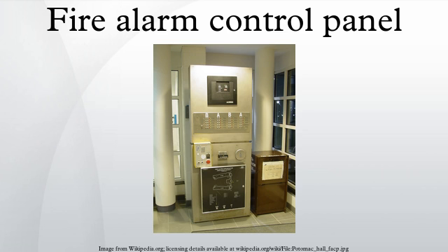A coded panel is similar in many ways to a modern conventional panel, except each zone was connected to its own code wheel, which, depending on the way the panel was set up, would either do sets of 4 rounds of code until the initiating pull station was reset or run continuously until the panel itself was reset. Large panels could take up an entire wall in a mechanical room, with dozens of code wheels. Lists of codes had to be maintained, sometimes with copies posted above pull stations.